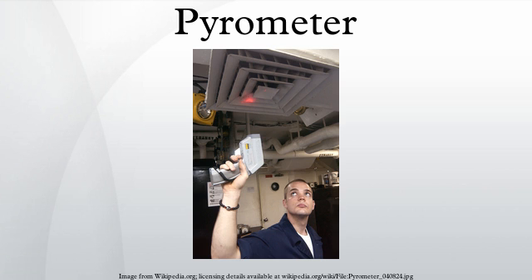It was calibrated to allow temperature to be inferred from the current. The temperature returned by the vanishing filament pyrometer and others of its kind, called brightness pyrometers, is dependent on the emissivity of the object. With greater use of brightness pyrometers, it became obvious that problems existed with relying on knowledge of the value of emissivity.